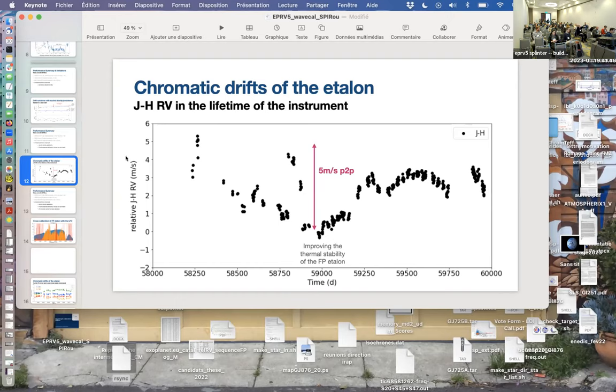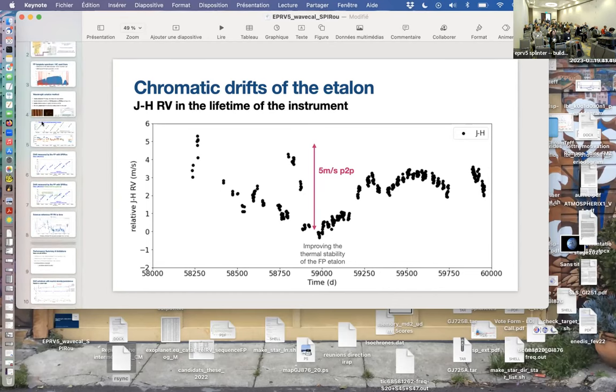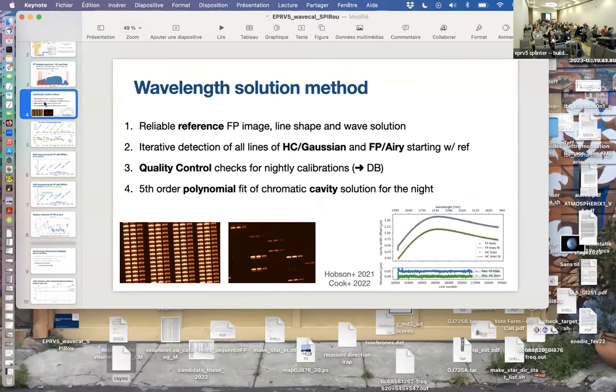Okay, yeah, just to clarify things on how it's corrected, we have, as Claire said, the starting point wavelength solution. Then you say, therefore, that with the Fabry-Pérot you're one number away from an absolute calibration. So you add a cavity, an achromatic change in the cavity length. With what Claire showed, it's to be revisited, but we add an achromatic change in the cavity length. So you're that number away from an absolute calibration. So we just say, oh, tonight we have zero cavity change.